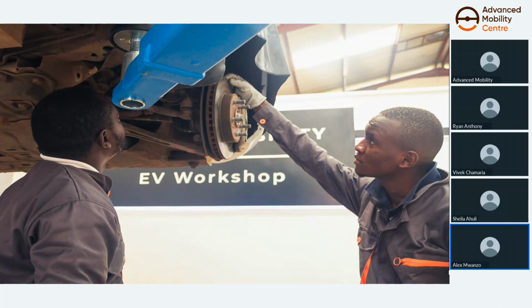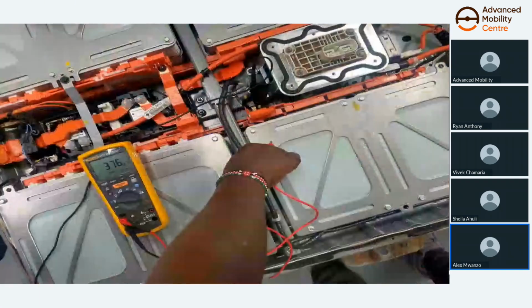So we are checking the battery pack. We did have an issue when we had floods 2 months back in Nairobi. The reason we don't have gloves at this point is, one, we've completely drained the battery, and two, we're checking for the insulation resistance where the battery would be leaking to ground.